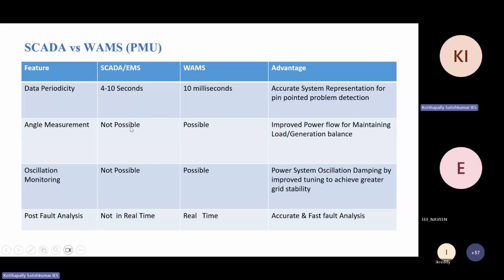In PMU, you will use GPS as a reference. So exactly at the same time, you will measure using GPS as your reference. It will give the signals to all PMUs at the same time. So all PMUs will measure at the same seconds, milliseconds, and microseconds. So you can compare the phase angle from one substation to another. So from Kashmir to Kanyakumari, from Gujarat to Assam, you can measure the phase angle between any substations.